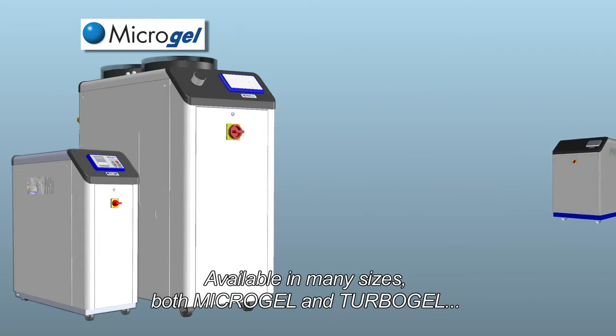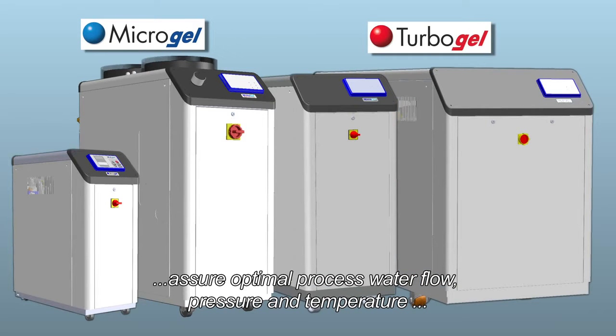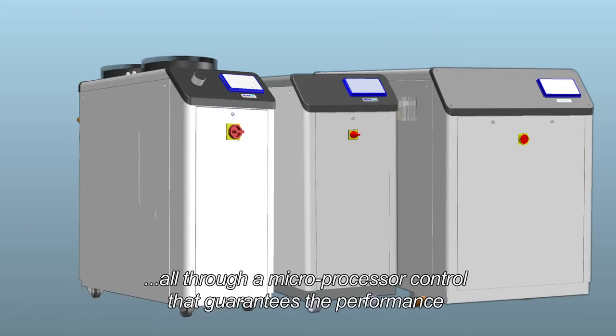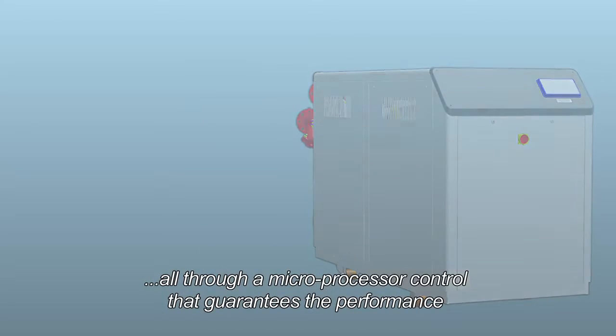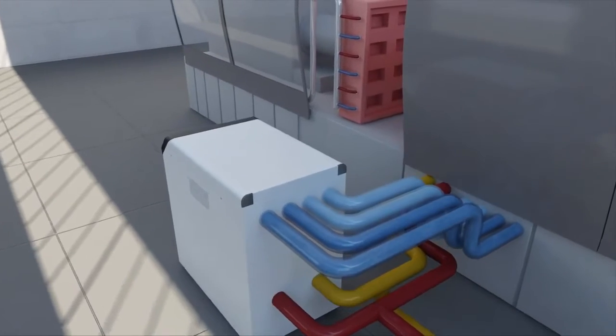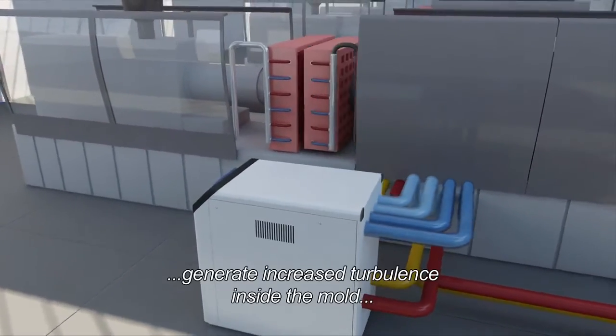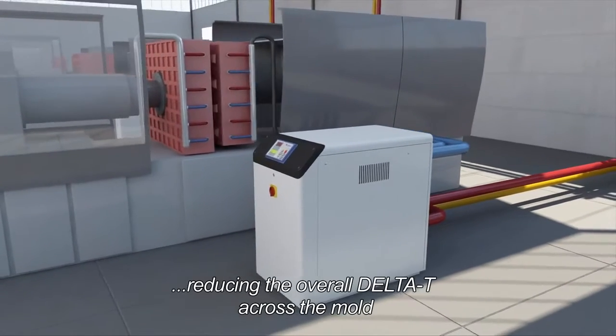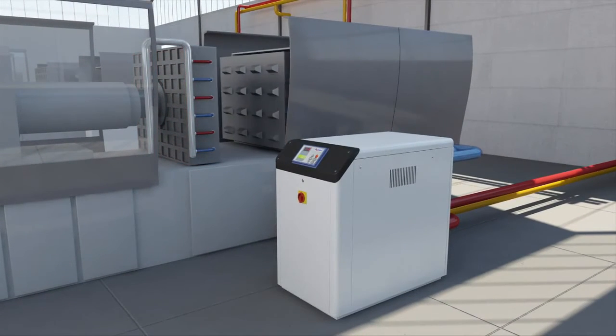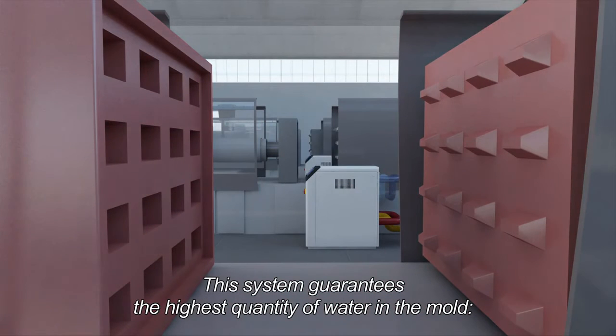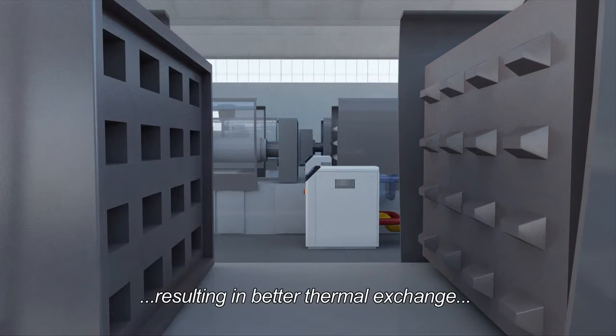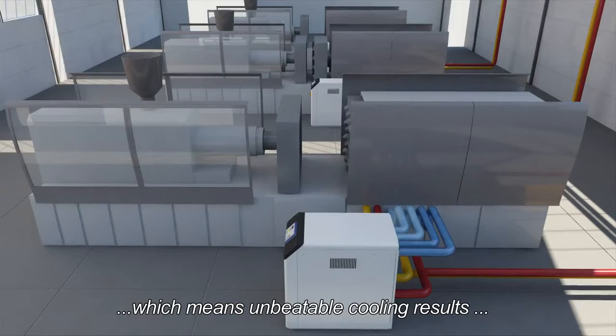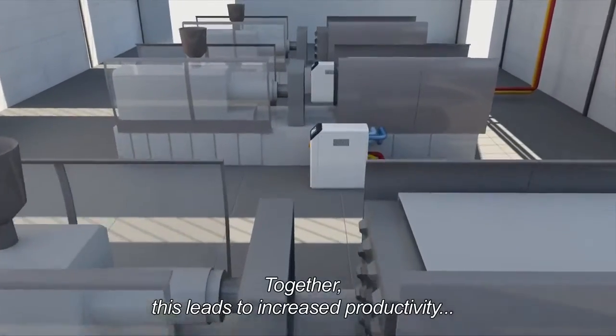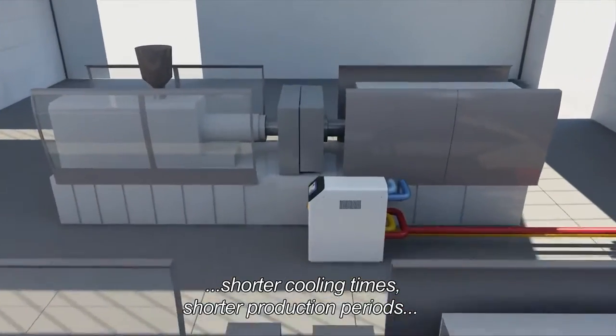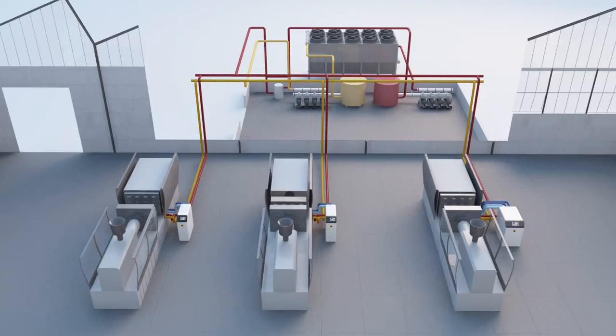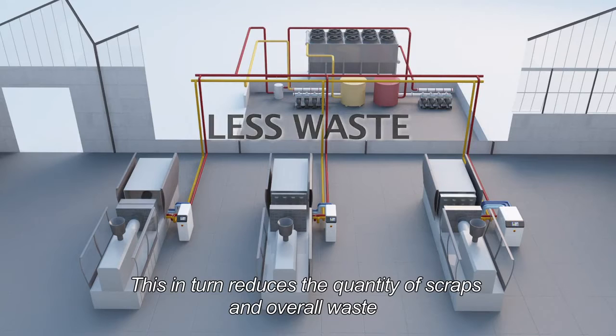Available in many sizes, both microgel and turbogel assure optimal process water flow, pressure, and temperature, all through a microprocessor control that guarantees the performance. Both microgel and turbogel units, thanks to the high flow rate of their dedicated pumps, generate increased turbulence inside the mold, reducing the overall delta T across the mold. This system guarantees the highest quantity of water in the mold, resulting in better thermal exchange and uniformity of the temperature in the mold, which means unbeatable cooling results. Together, this leads to increased productivity, shorter cooling times, shorter production periods, and more precise cooling control. This, in turn, reduces the quantity of scrap and overall waste.